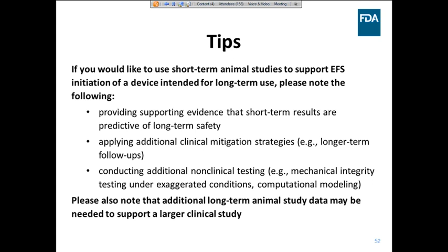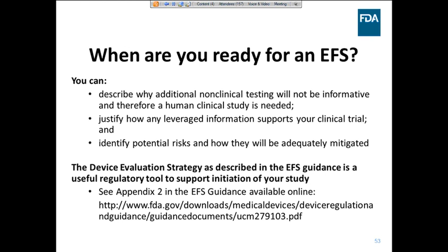So when do you know that you're ready for an EFS? Well, it's generally when you can describe why additional non-clinical testing will not be informative and therefore a human clinical study is necessary. You can also justify how any leveraged information supports your clinical trial, and you can identify the potential risks and how they will be adequately mitigated. We recommend that you communicate these points to us using a device evaluation strategy as described in the EFS guidance, and the link is provided in this slide here.